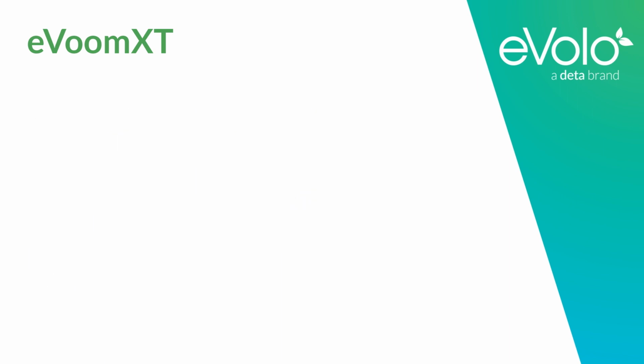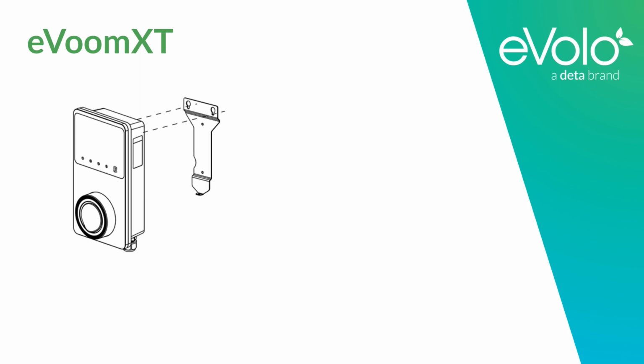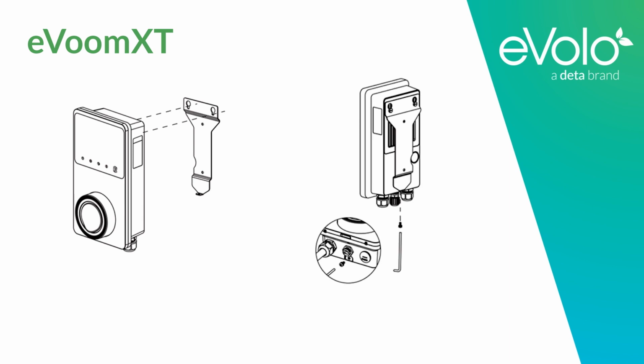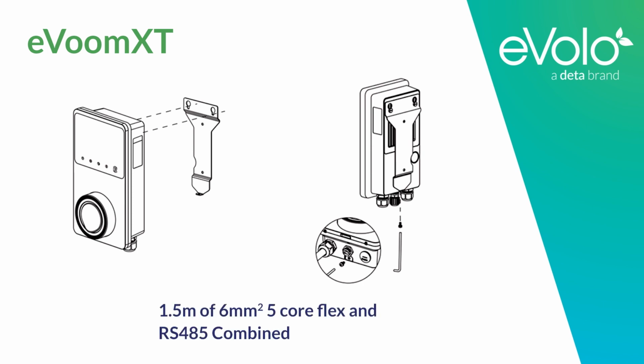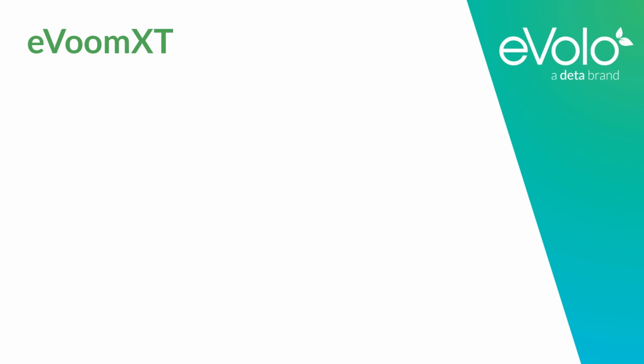Installation of this charge point is just as straightforward as the eVoom and eDock. Available with a mounting bracket that fits to a wall or post, the eVoom XT simply hooks on and uses a set of security screws to secure it. For wiring, it comes pre-wired with 1.5 metres of 5-core 6mm cable for three-phase supply. If using the eVoom XT on a single-phase supply, safely terminate the non-used conductors during installation. This cable has RS485 data conductors combined.